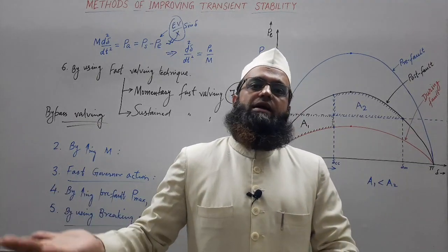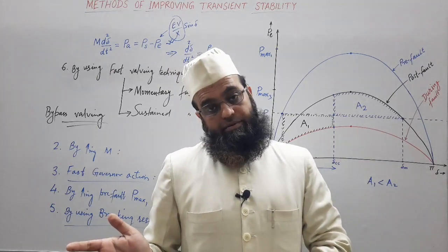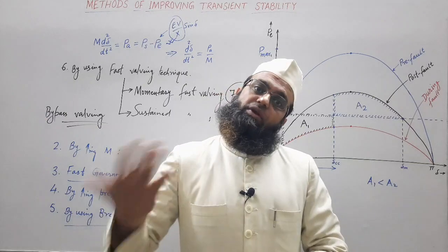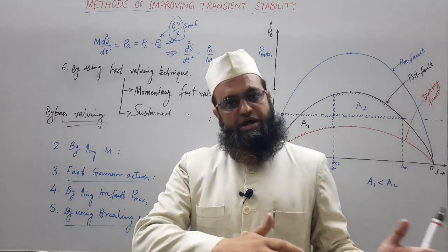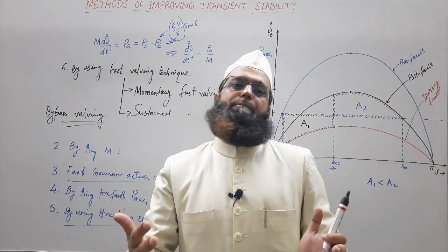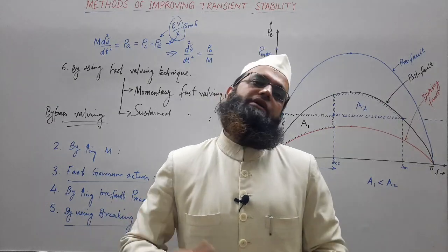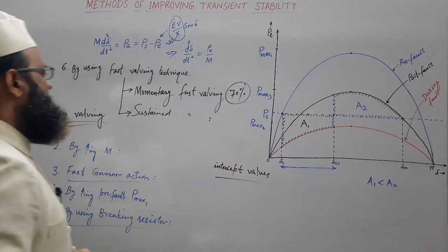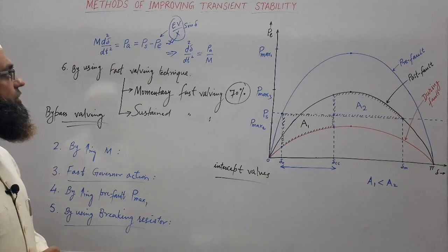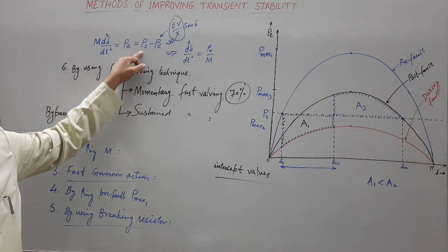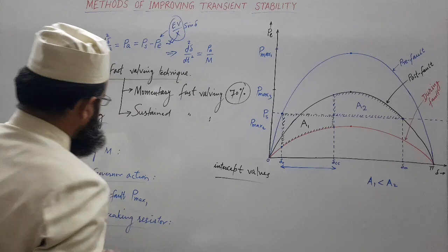Instead of sending it to the turbine, we are directly sending it to the condenser, and as soon as the situation is restored to normal, we are again quickly capable of feeding the required amount of steam to the turbine. Fine. So this way we are controlling this shaft power from the mechanical side with the help of this technique.